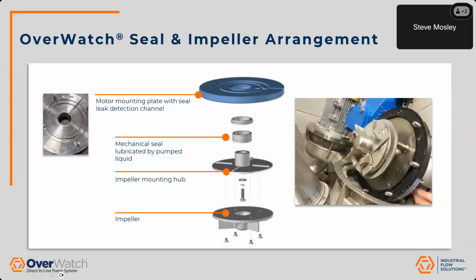Next, we're going to go into the assembly of this hydraulic end. The maintenance on this OverWatch system is very easy. All of the hydraulic components are close coupled to the motor, and you can remove that motor typically with about eight nuts that come off, and you can remove that entire motor from the housing. When we ship the unit, we do include a closing plate, so while you're working on that one motor, you could seal up that open volute and then allow the other pump to operate in its normal capacity while maintaining the second motor.